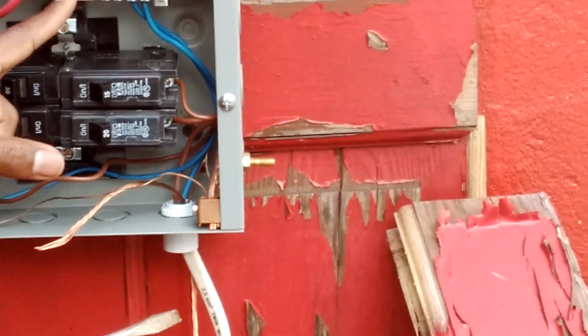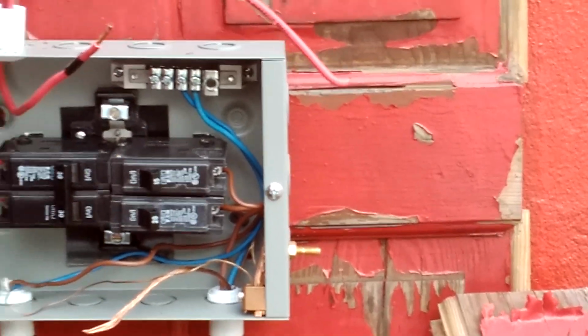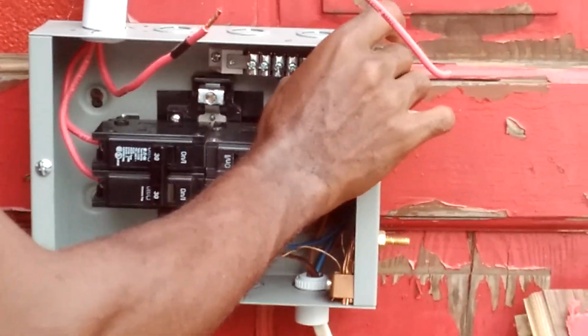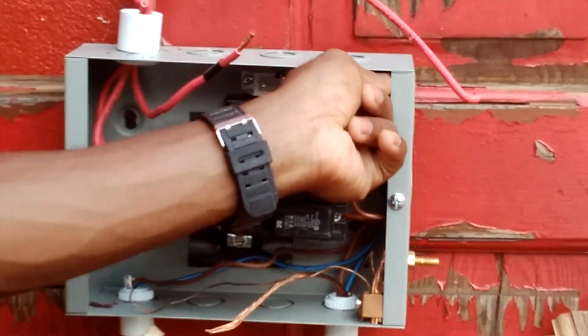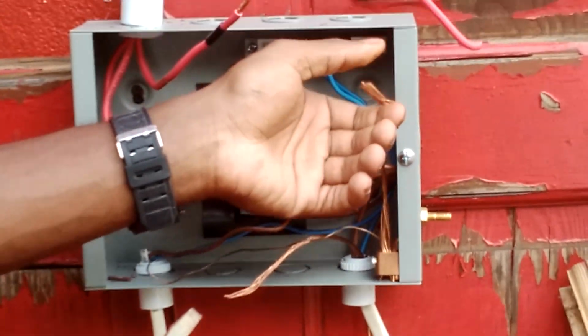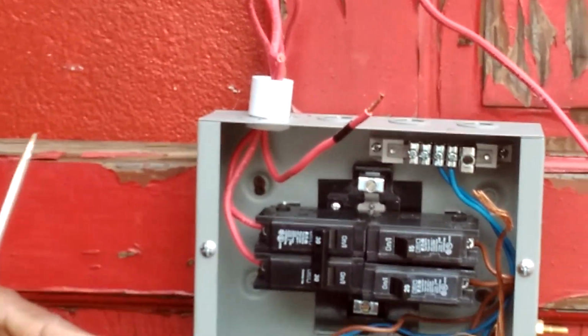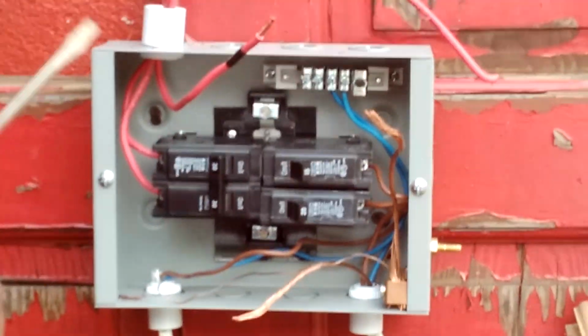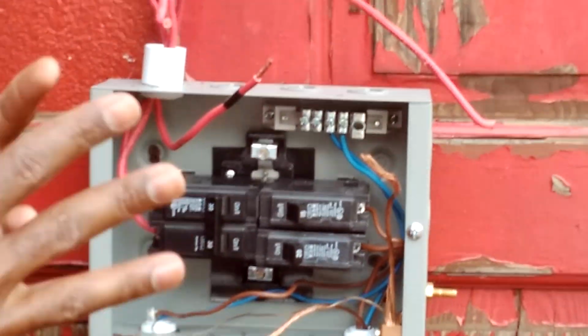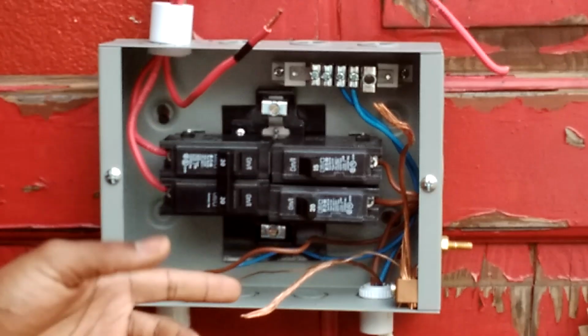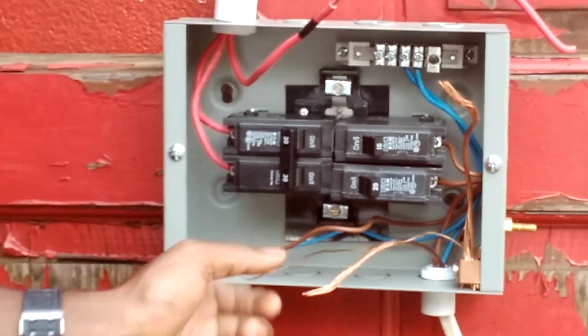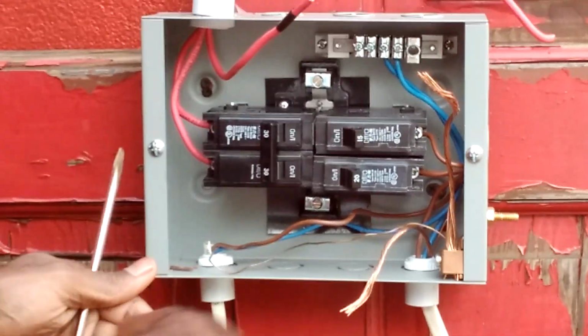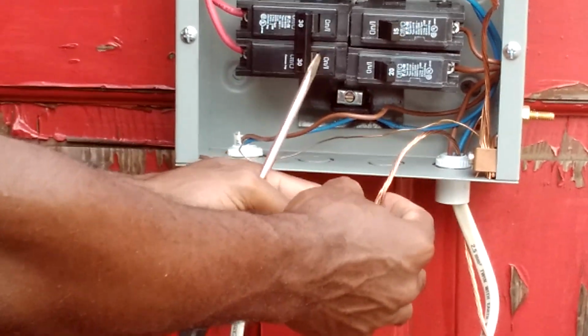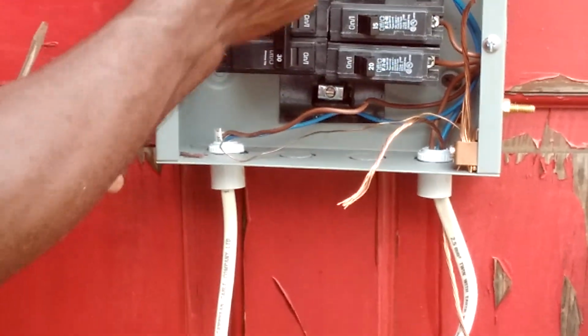First, we have the earth wire coming in from the ground, the main ground. It's a rule in the Jamaican electrical code that the ground wire coming from the ground - this wire right here - has no sleeving and is the same size as a 6mm wire.